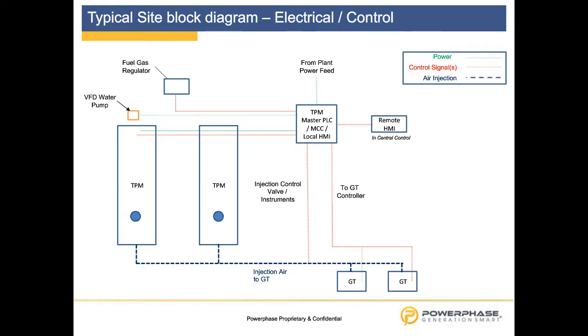Important to know here is that we don't interfere with the existing GT controller. What we do is only read data out of the gas turbine controller, and with this data we control our system and make the operation safe. We have several levels of integration. We can integrate it into the master, into your control room. We can integrate it in the DCS. We can make an automatic ramp up. We can even have grid control of the TPM and the air injection. So we are flexible and follow the requirements of the power station. Once more, important is that we don't interfere in the existing GT control logic.